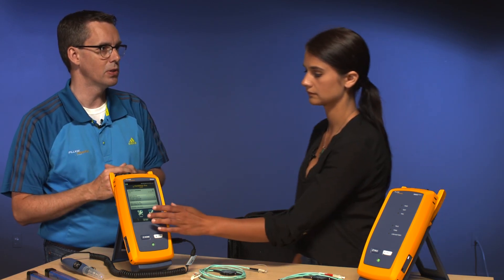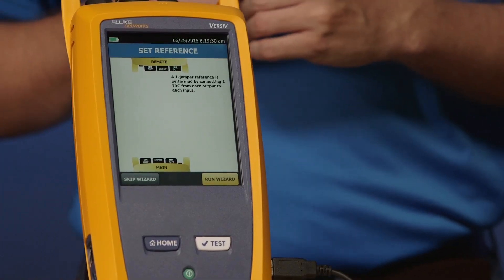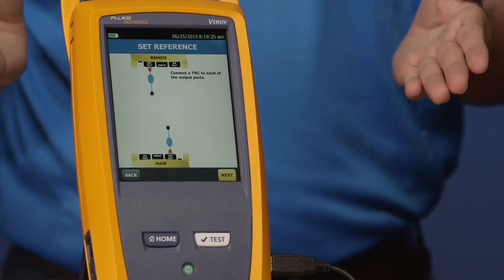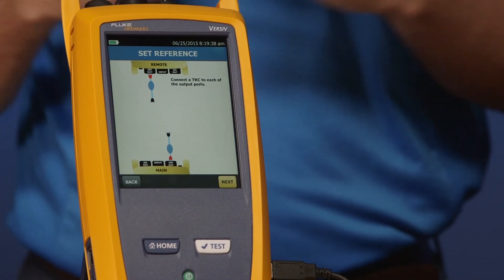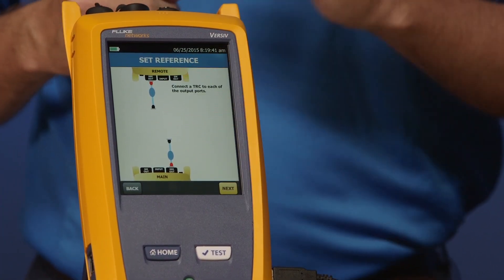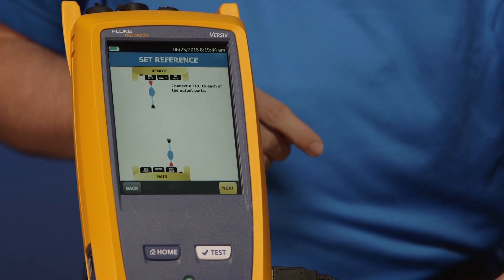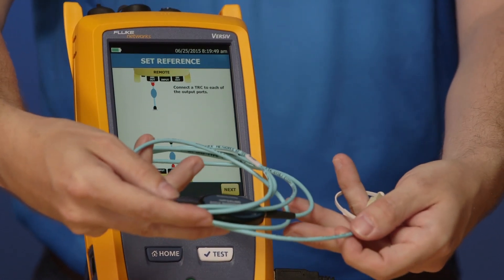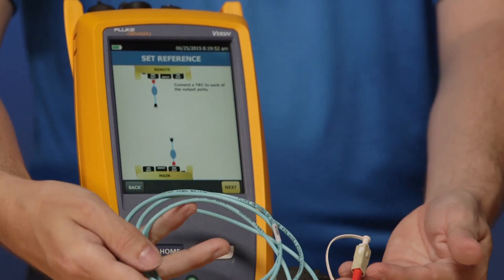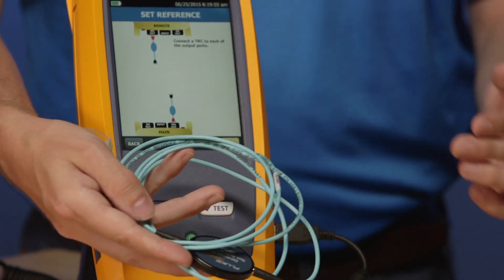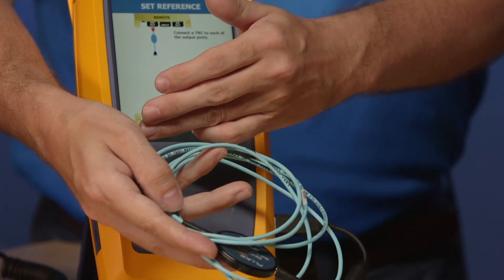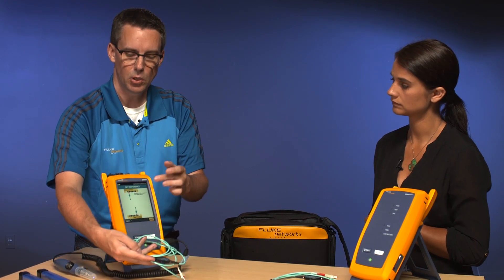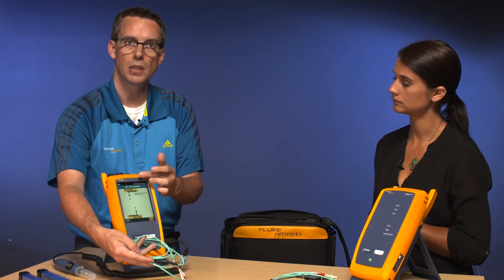Go ahead and tap Set Reference and we're going to run the wizard. The first thing it's going to do is tell you — as you see on the animation — that you need to connect your cords to the output ports. On the drawing on the screen you'll see the little puck, which is this thing here. We've got a 50-50 chance of getting this the right way around and it does actually matter. You'll notice on our cords that one end is red and the other is black. The way I like to remember this: red is hot, black is cold. So the red is connected to the output port on the instrument, which you can also see on the LCD.